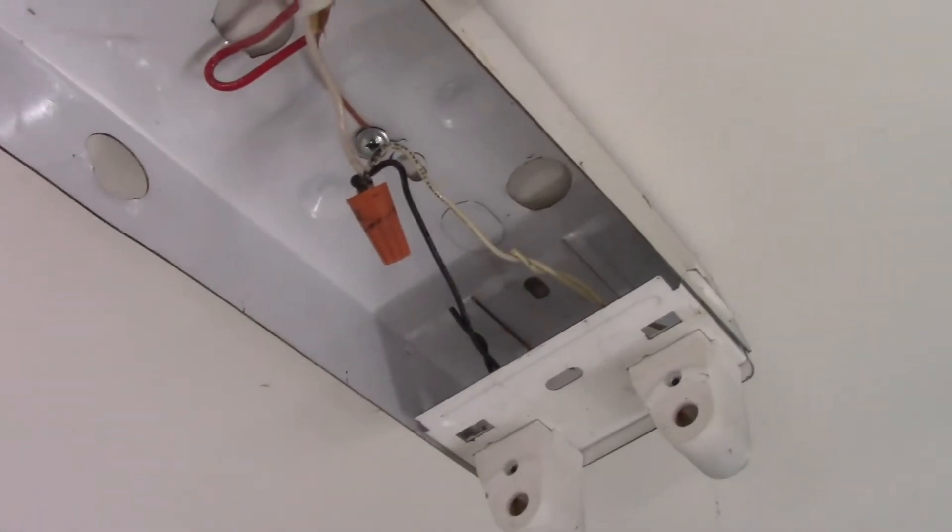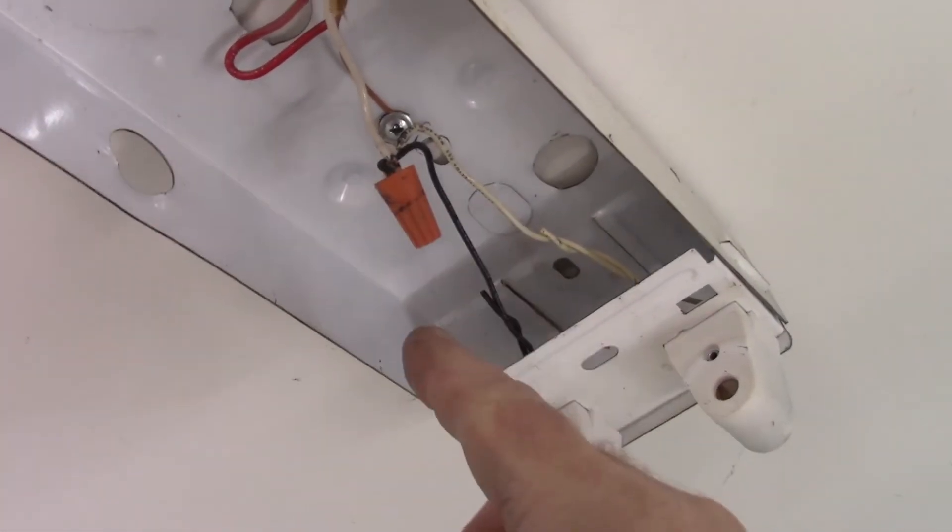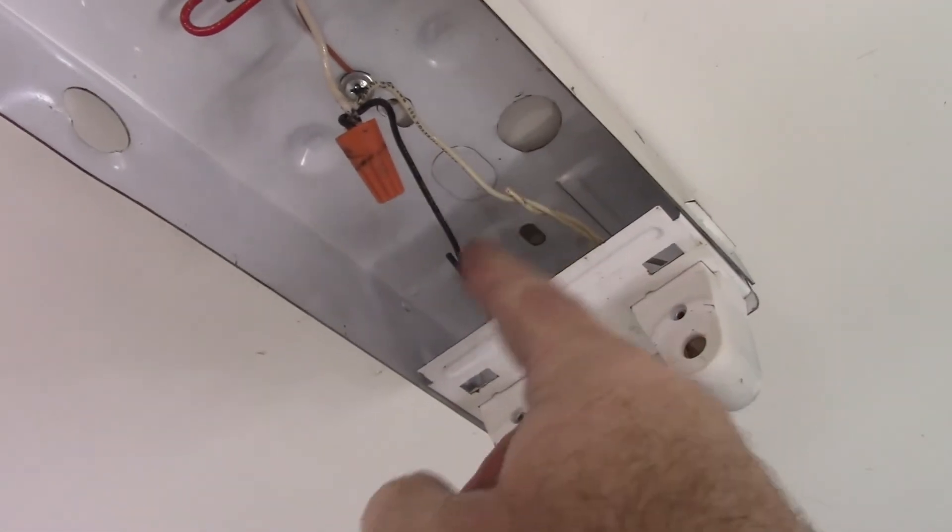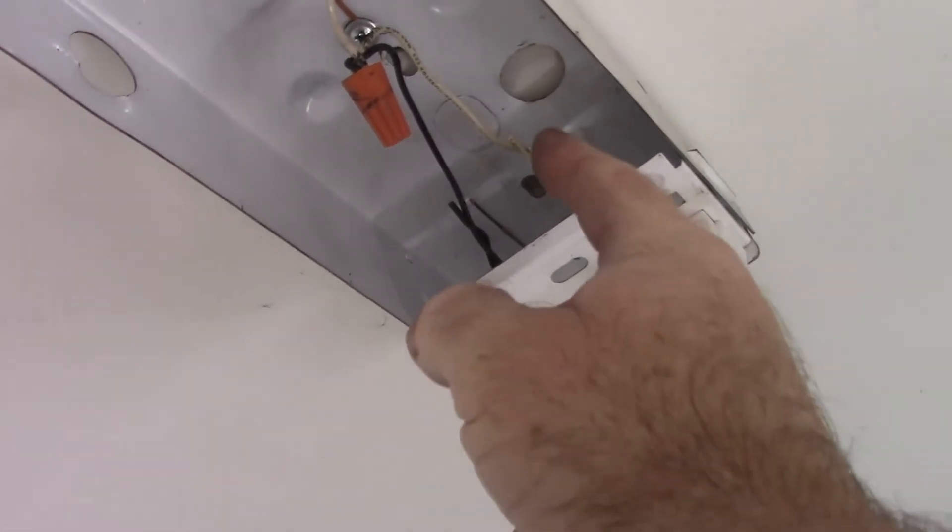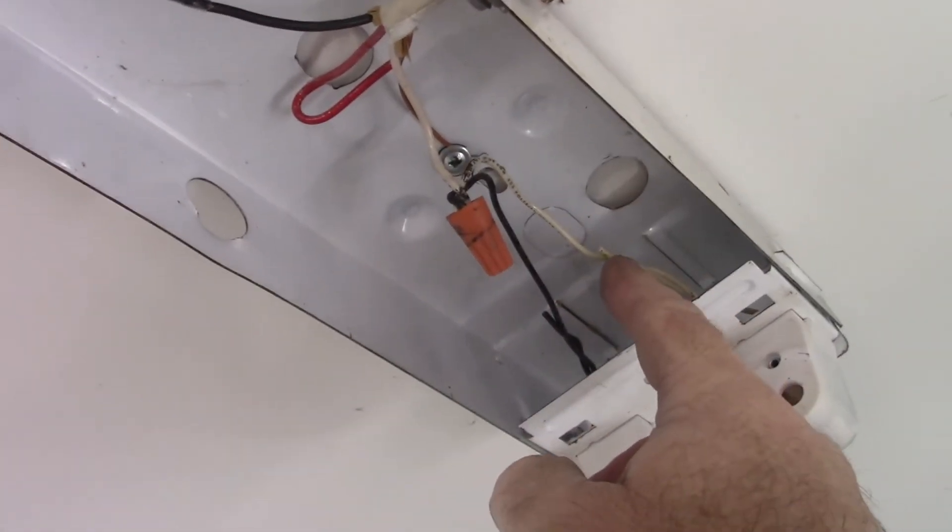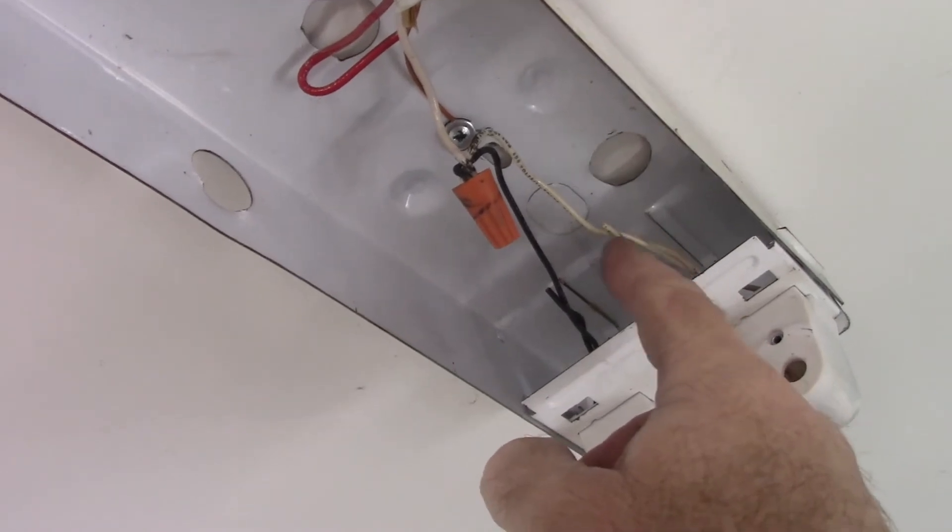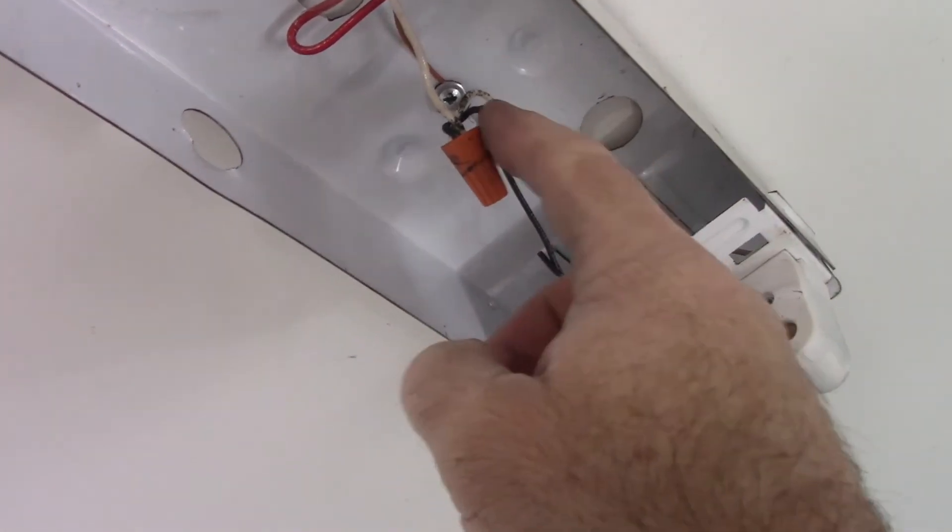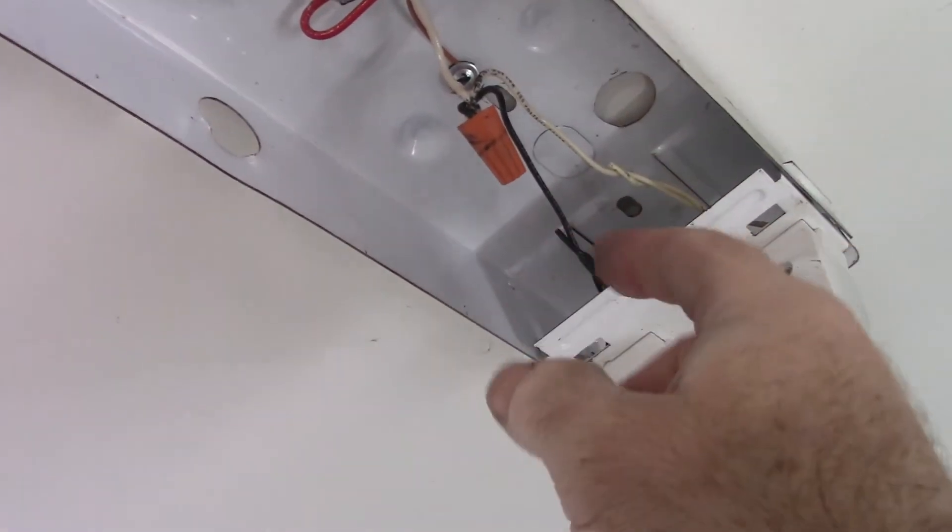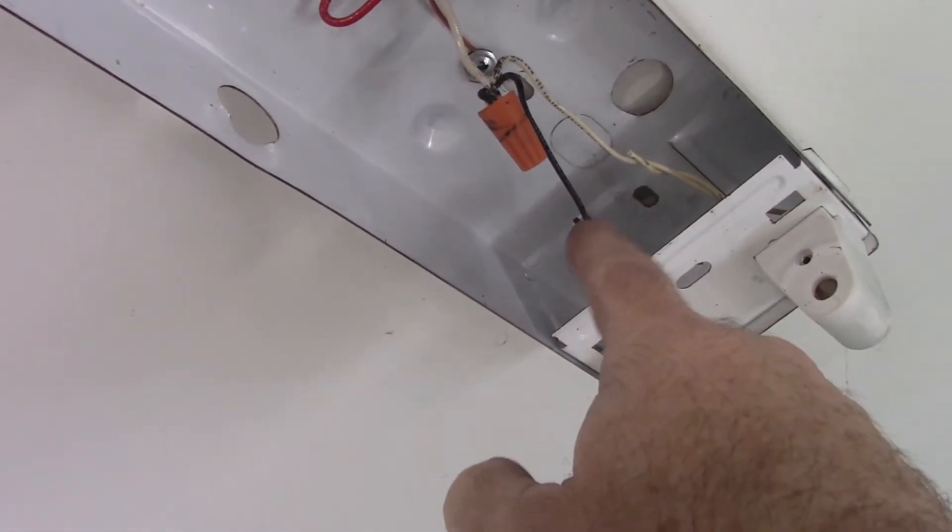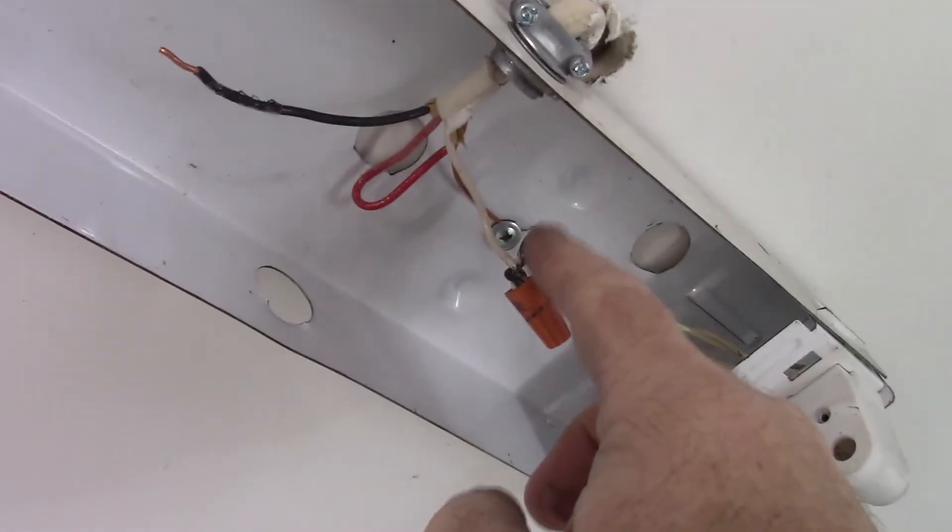Hopefully you can see this, but what I did is I cut the wires off and both of the pigtails from these tombstones are now connected to the white lead on this end. I also took the ends of the pieces I cut off and wrapped them around these two leads. You could connect all four into there if you wanted to, but you don't need to. I will take some black tape and wrap around these ends and also around the wire nut.